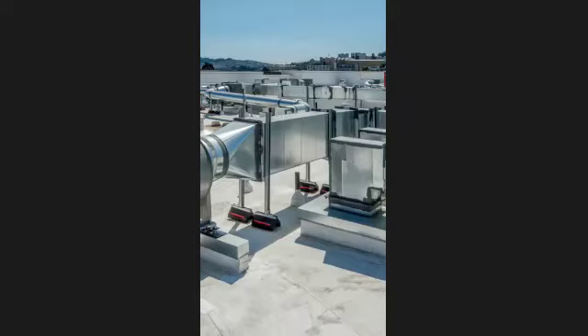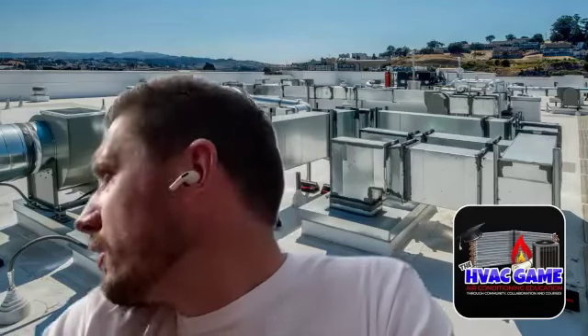Well, you check the data tag. You check the data tag for how much it's supposed to be, or you check the manual on your subcool. It's usually stated. If you're working on rooftop units, it's usually on your data tag. If you're working on split systems, it's usually on your condenser data tag. Otherwise, you can always Google it, or you can call the manufacturer.